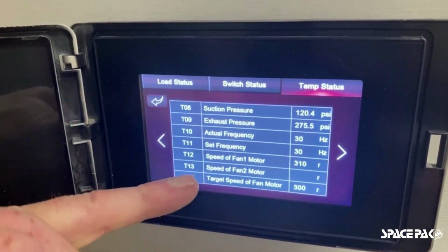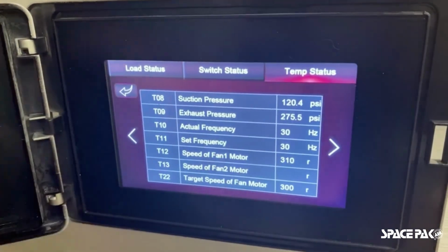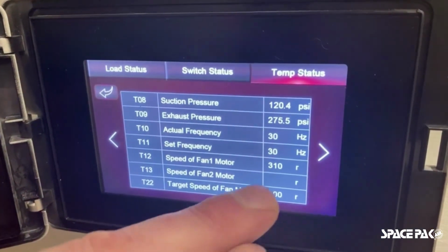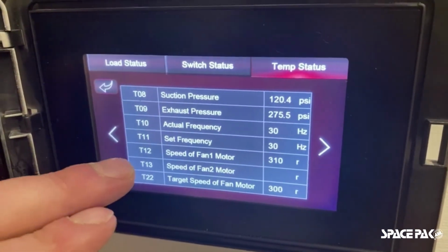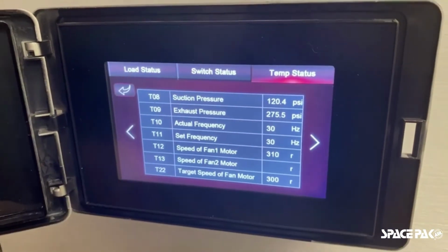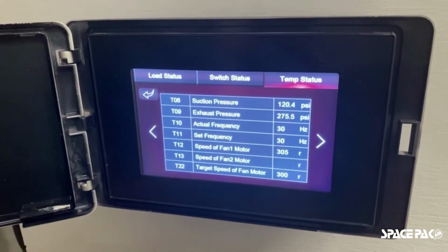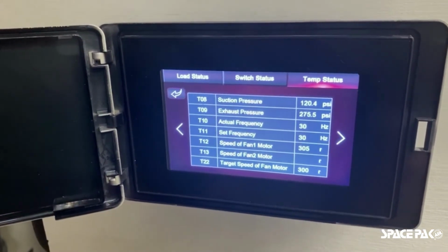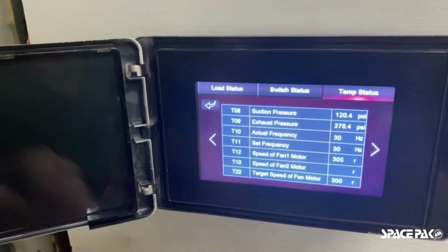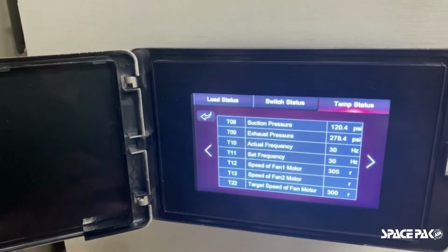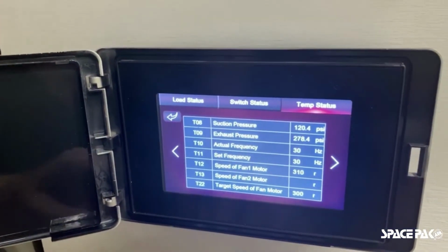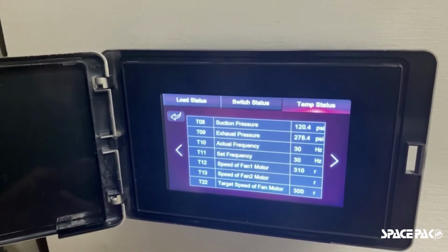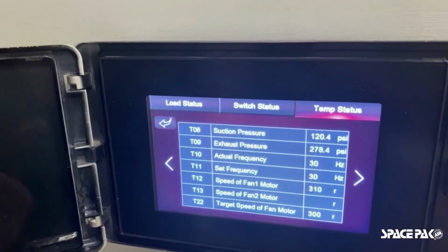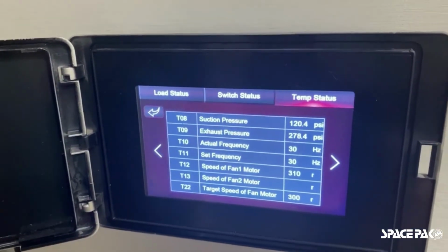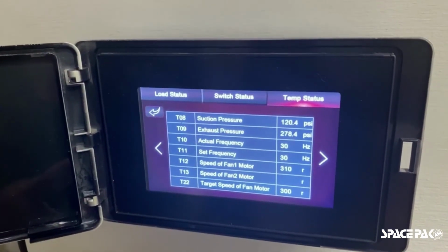Something that we know here right now, we're currently running at low speed, right? Set frequency is at 30 hertz. Our actual frequency is at 30 hertz, I'm sorry. The range can go anywhere from 30 to 90 hertz. Also fan speed. This SIM 036 has one fan. We're currently at 310 revolutions. Okay, we can go up as high as 850 and as low as 100.